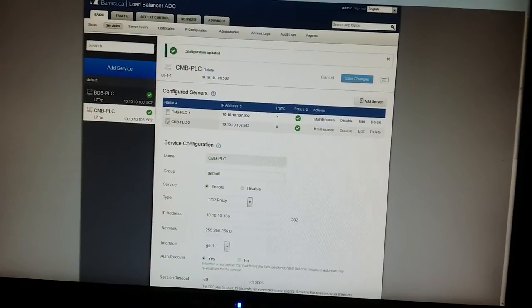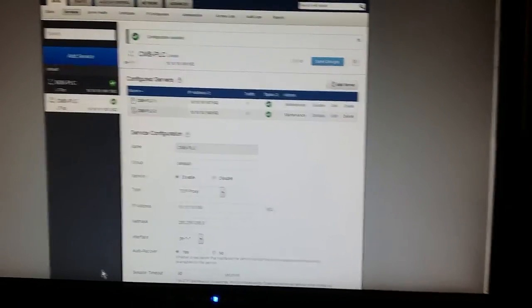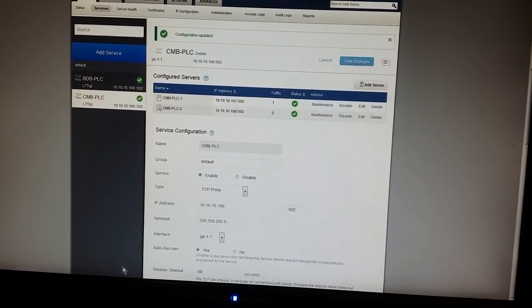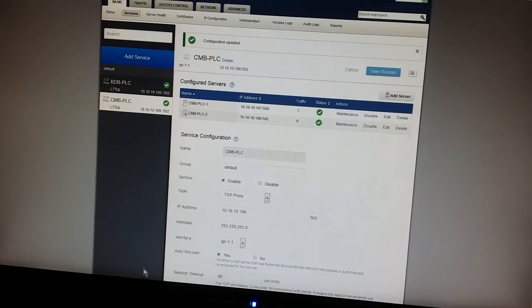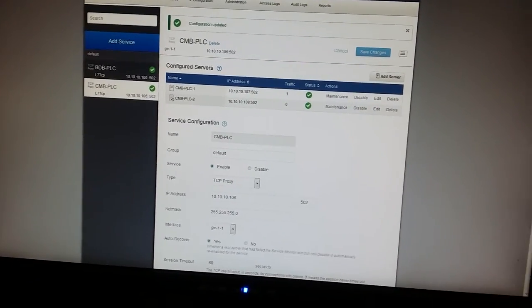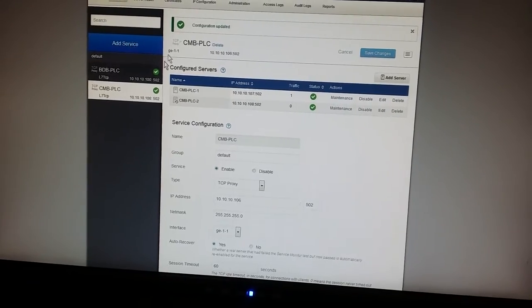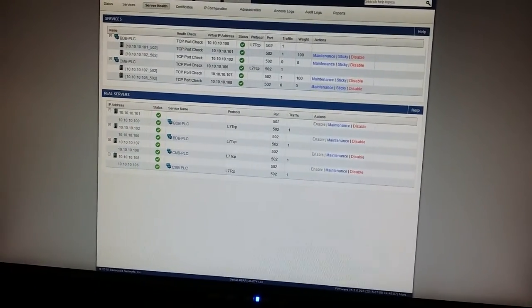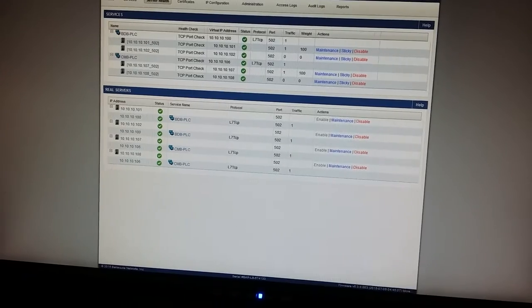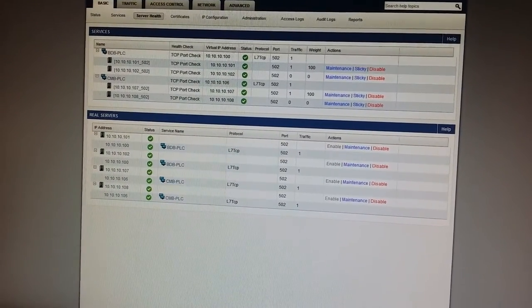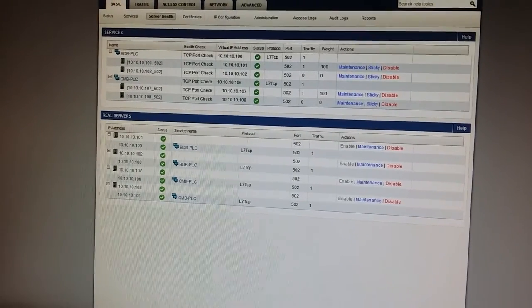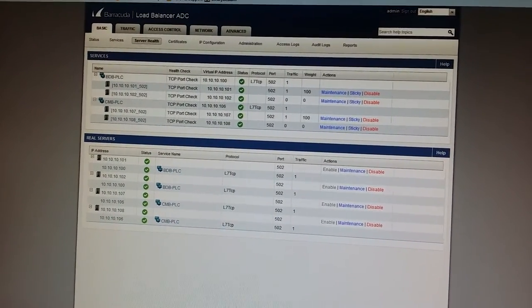So how was this accomplished? If you log into the Barracuda I was able to create two separate layer 4 TCP proxy services. And then I just mapped both PLCs as real servers to each of those services. And then you have to designate one of the servers on each service as a backup server.